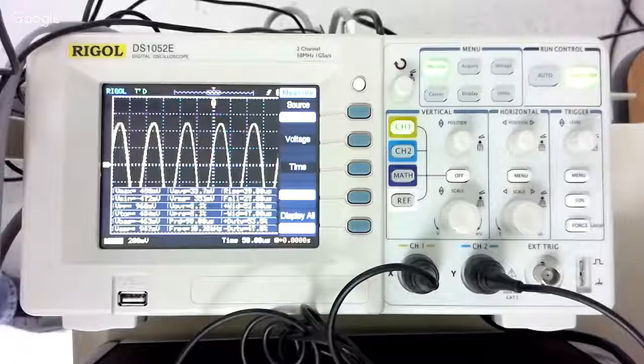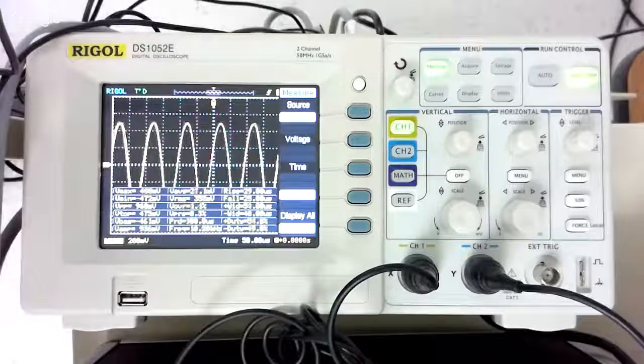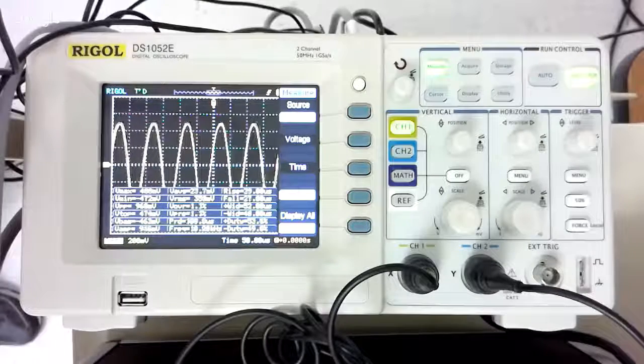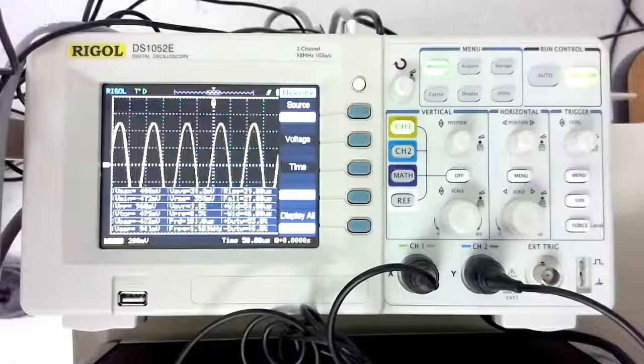The reason you want to do a floating point measurement is, say you want to measure phase to phase in a 3-phase circuit. This ground probe is tied to chassis ground, so if you were to measure phase to phase, you would take one of your phases to ground, which would be a short, so that's not something we'd want to do.